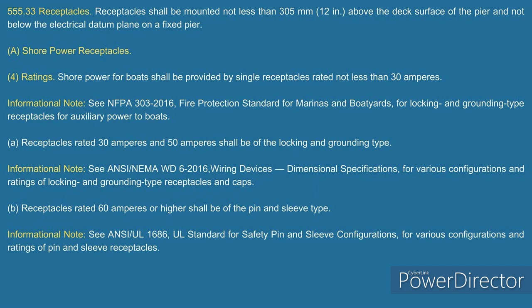Yeah, and I want to put another part on this. Also, it's interesting. When you're looking at the receptacle, that shore power receptacle is, when you look at 4A, it tells you that receptacle is rated at 30 amps and 50 amperes and shall be of the locking and grounding type. That means it's going to lock in. There's a reason that the receptacles are designed a certain way. And basically what they're telling you is you're not really going to be, as the owner of that slip, cord and plug connecting that, you're going to be doing that to the unit that's there, that's providing the shore power. And that's the reason that there's no GFCI protection.